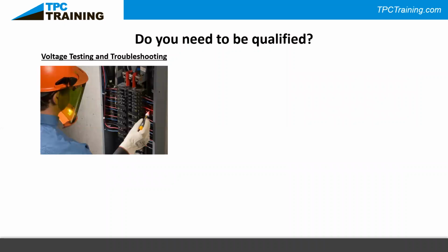Voltage testing and troubleshooting inside of a panel. Let's say it's a 120 volt panel with a red, blue, and white, and you're testing for voltage in there with all your PPE on. Do you need to be qualified to do this? The answer is absolutely yes. Anything greater than 50 volts, phase to phase or phase to ground, you need to be qualified to do voltage testing and troubleshooting. You can look right in Article 110.4a to show that.